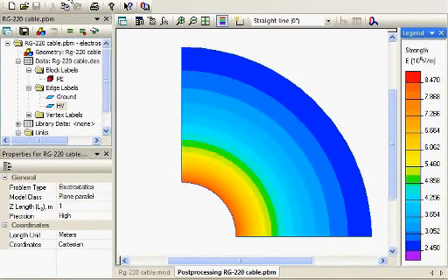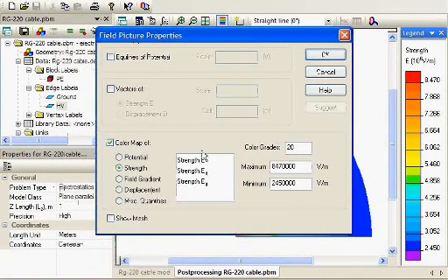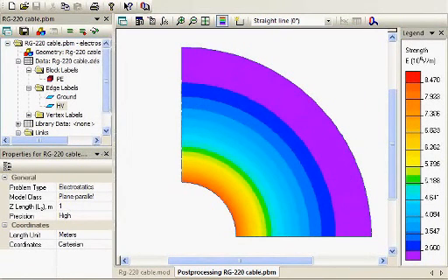And we can check that in this case, again, by setting the minimum here at the 3 megavolts per meter, and you can see it's not quite there yet, but if the voltage goes up any higher, we're going to start to see that those fields there get up to that threshold, and so that might be a problem for the cable. And in real life, some cable manufacturers will apply a layer of semiconducting material directly on the dielectric at that point, and that's part of the reasoning behind that, so it'll help avoid these issues. Then the semiconducting material will avoid the corona inception there, since it is at the ground potential.